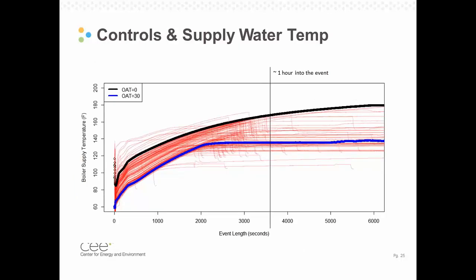The next thing that was really important was an internal boiler control that was key to the performance. This is a plot looking at just one site, but it was typical of all the as-found sites and even all the boilers we monitored across the project. It shows the supply water temperature coming out of the boiler over time. Each individual line on here, red, blue, black, is a single heating event. That's a single time your thermostat comes on and calls for heat, and you can see the length of the event across the x-axis, in seconds. The boiler turns on, provides heat to the home, and then the thermostat is met and the boiler turns off.